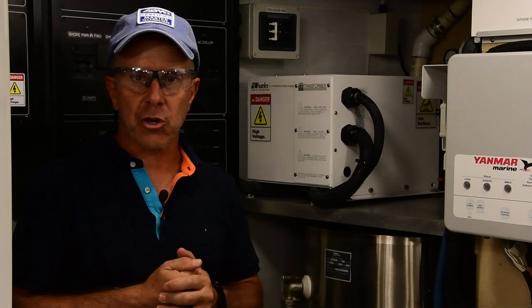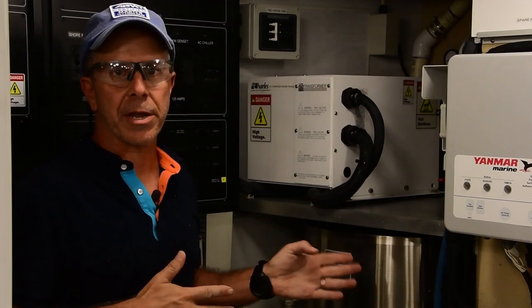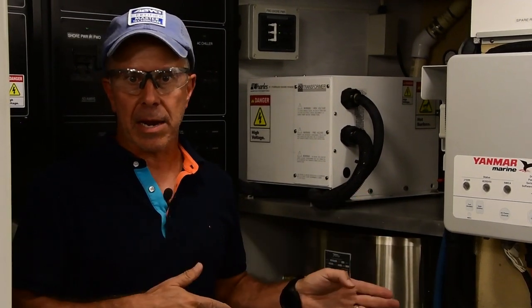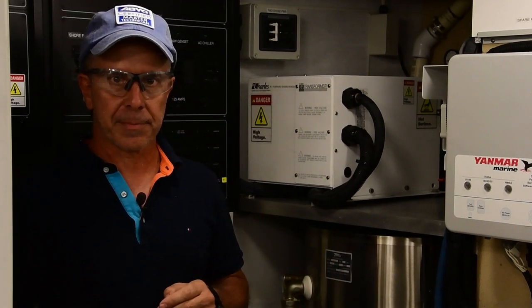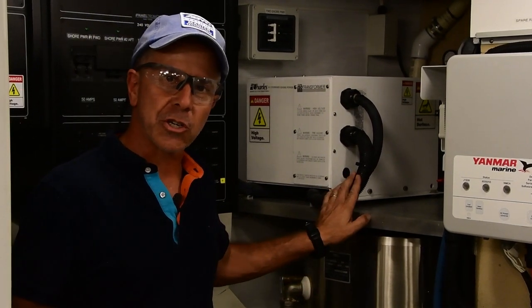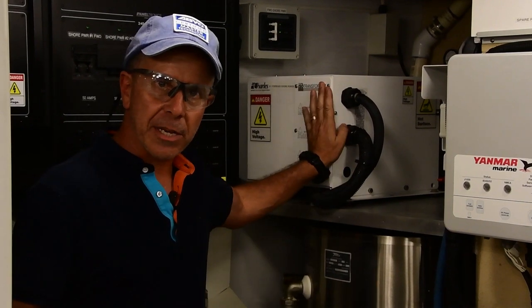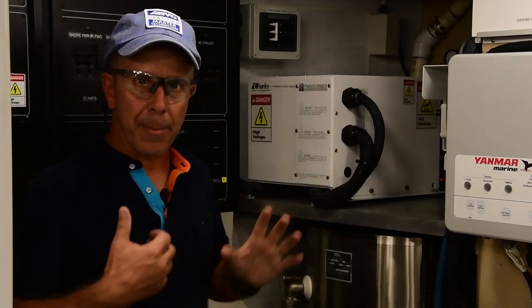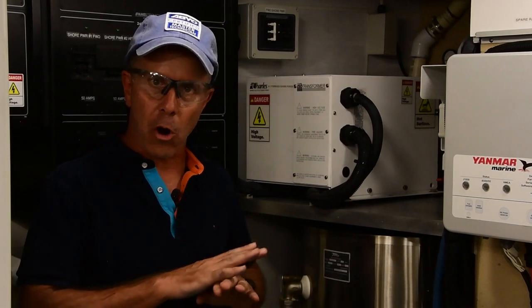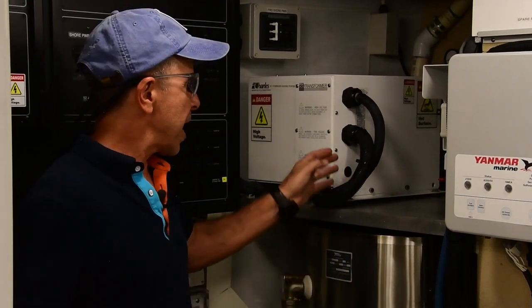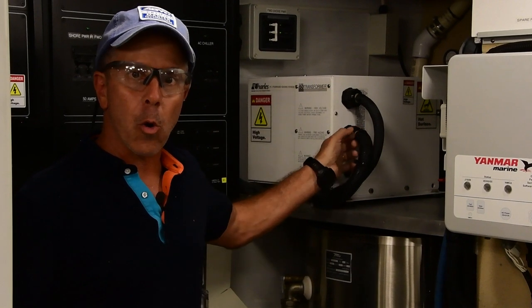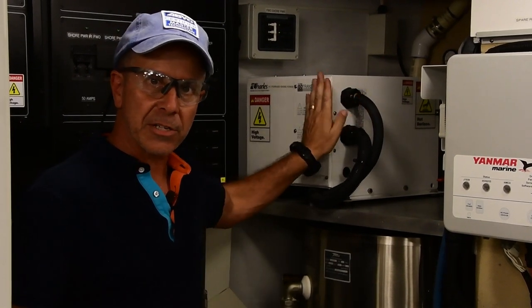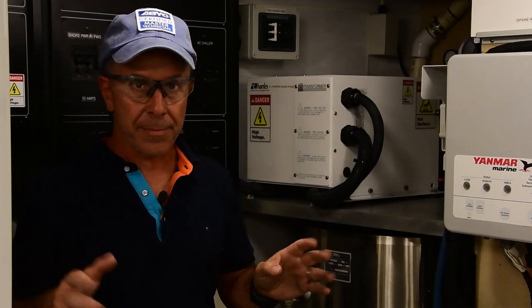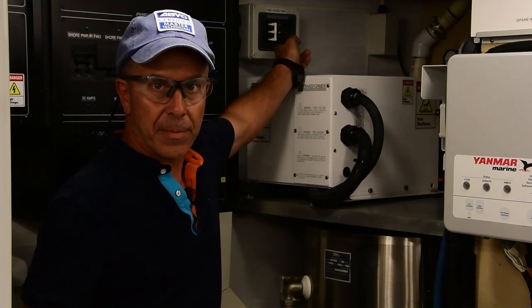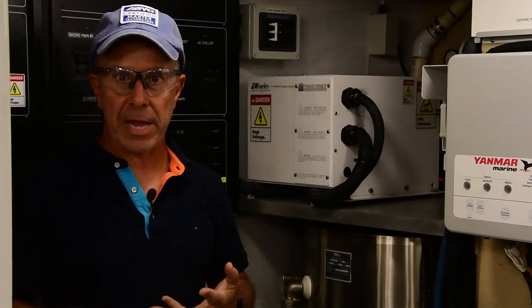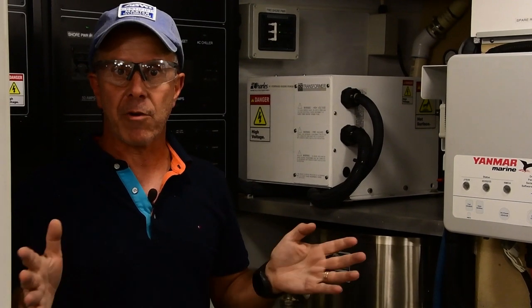As a final feature worth mentioning when we're talking about transformers, and again, isolation versus polarization. For a polarization transformer, the chassis or the metallic enclosure, the boat's ground, and the dock ground are all common. So if an energized wire on the primary or the secondary makes contact with the enclosure, in theory, it should trip the circuit breaker for either the inlet or the outlet on the transformer, rendering it safe.